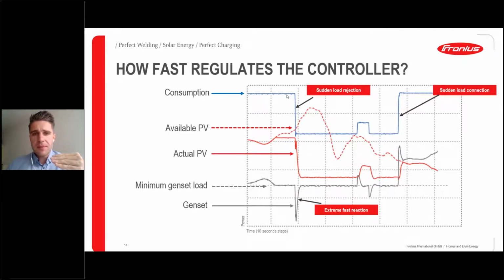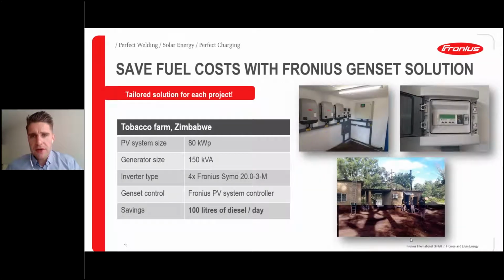And if there is, for example, a sudden load rejection here, but on the other hand, you would have good PV yield at the moment, the controller has the main task, of course, to protect this genset, and therefore it regulates down the actual PV. That happens within very, very few seconds, and therefore you have again this stable operation mode of the genset, which has, of course, highest priority within this system. Just one quick graph.